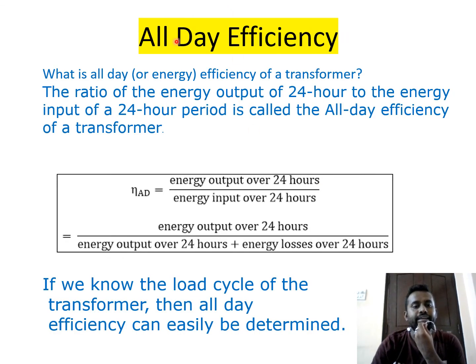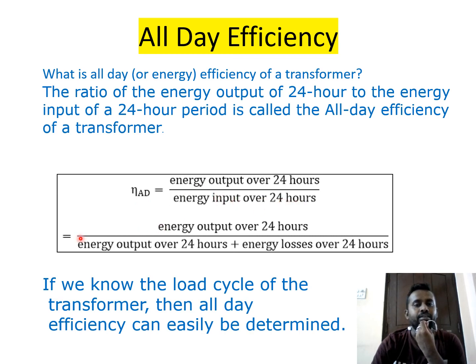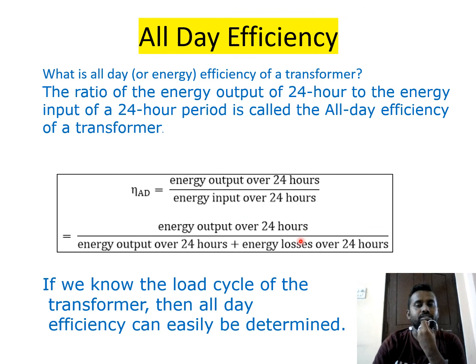All-day efficiency is the ratio of energy output over 24 hours to energy input over 24 hours: η_all-day = Energy output (24 h) / Energy input (24 h) = Energy output (24 h) / [Energy output (24 h) + Energy losses (24 h)]. If the load profile of the transformer is known, all-day efficiency can be easily determined.